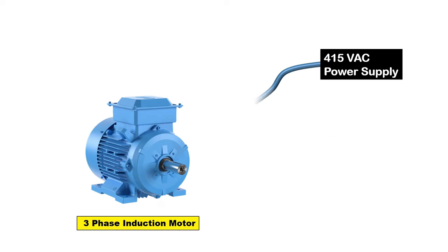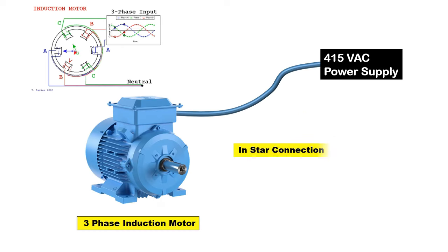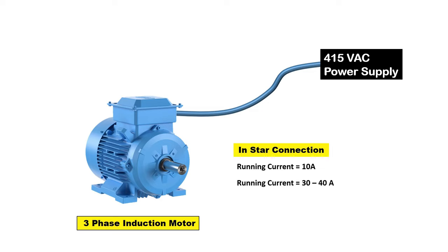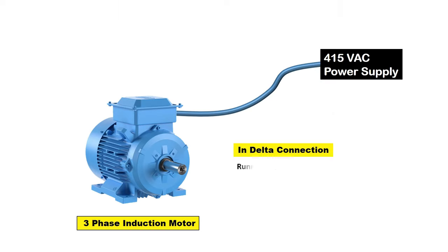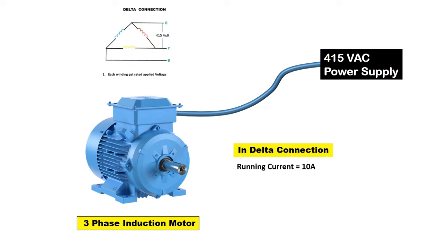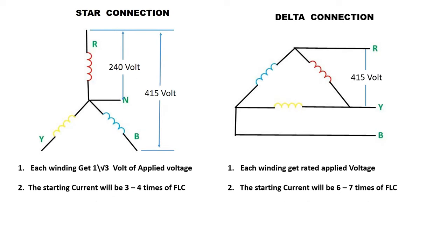Suppose you have a motor and the running current of that motor is around 10 ampere. But when you start this motor, at the starting time current can be multiples. On running, 10 ampere current flows, but 3 to 4 times of this current will flow at starting time in star connection. If you connected motor winding in delta, then the starting current of your motor will be 6 to 7 times of FLC. So if running current is 10 ampere, when you start this motor in delta connection, then 60 to 70 ampere current will flow at starting time.